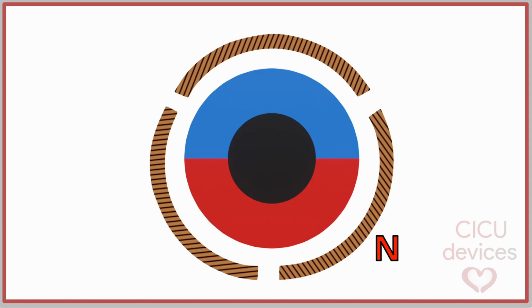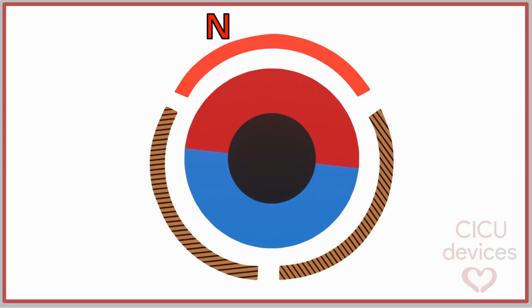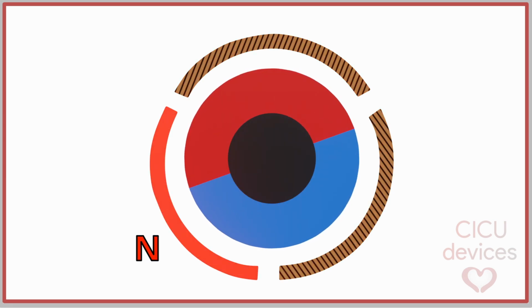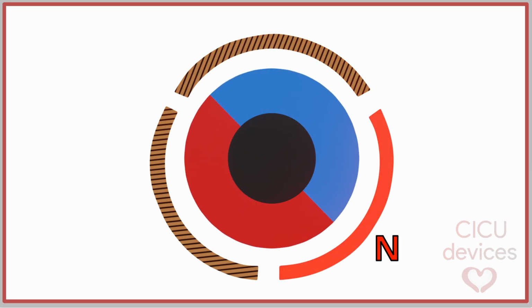In this way, the operation of the motor is as presented in this animation. The stator, powered by an external three-phase electric source, generates magnetic fields that interact with the permanent magnet of the rotor, inducing rotational motion, causing the shaft to rotate, which in turn drives the impeller within the cylindrical pump housing.